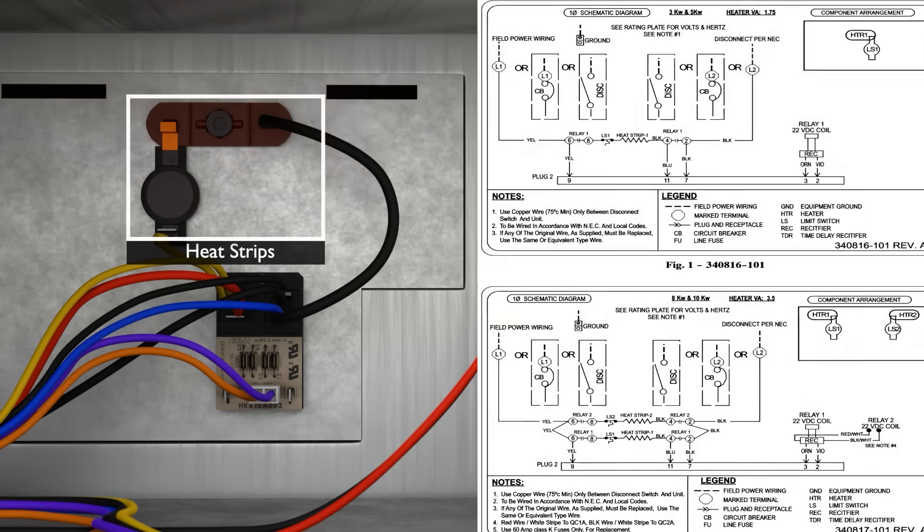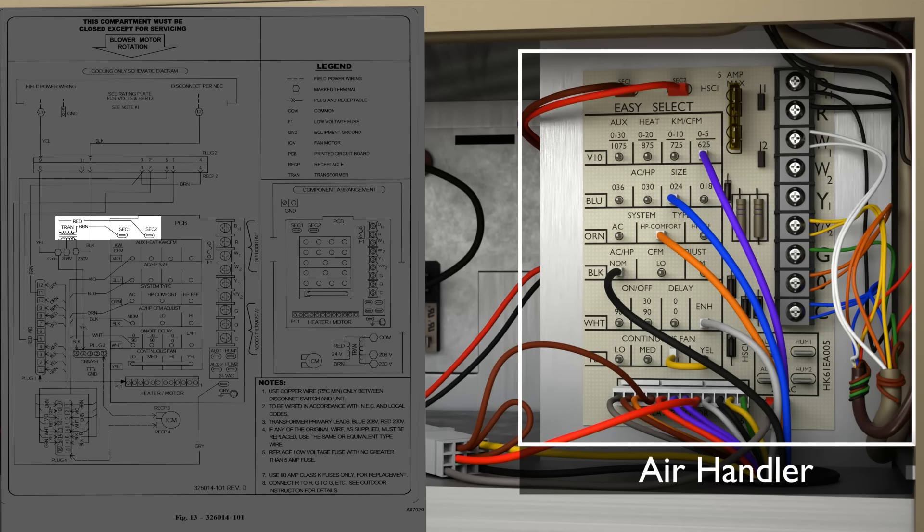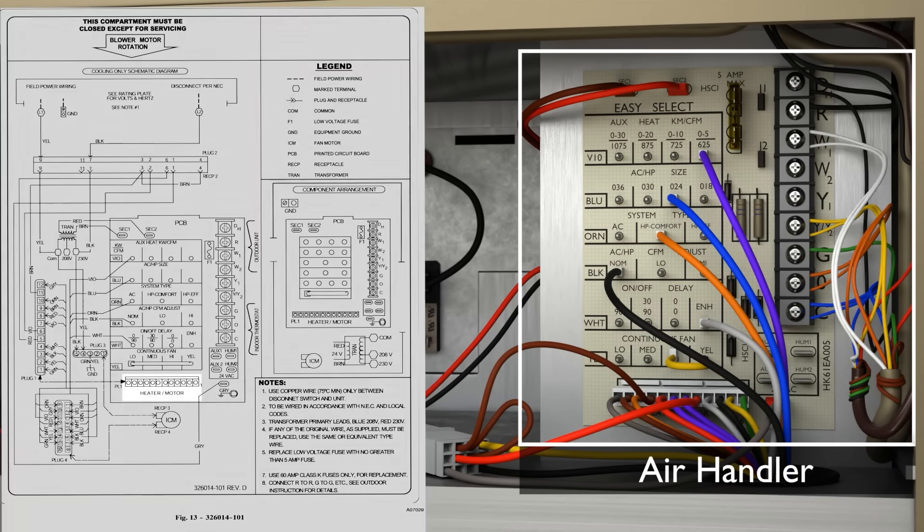Next, we show our integrated circuit board for our air handler. You can see our 24-volt power coming into the top at SEC1 and SEC2 from the transformer. Our 5-amp fuse and our terminal block for our low-voltage connections, as well as the plug that goes to the heater and motor.